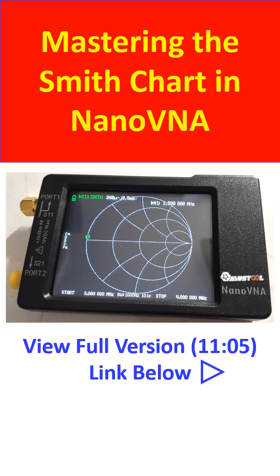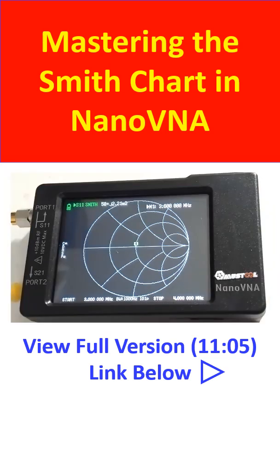Remove the open SMA connector and connect the short SMA connector instead. The marker will be seen at the opposite end of the Smith chart. After that, remove the short SMA connector and connect the load SMA connector in its place. Now the marker can be seen at the center of the Smith chart.